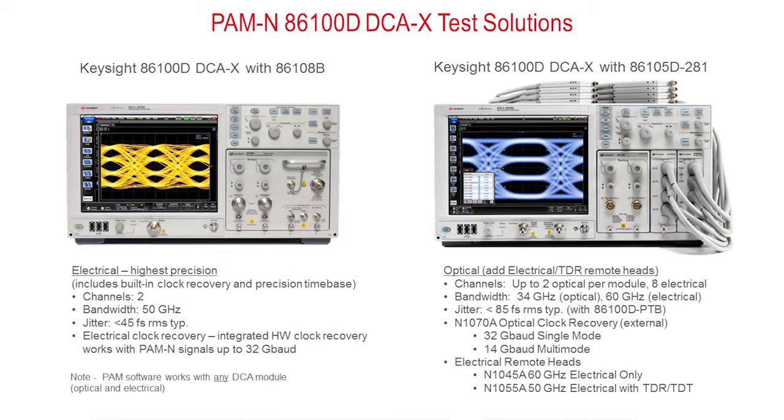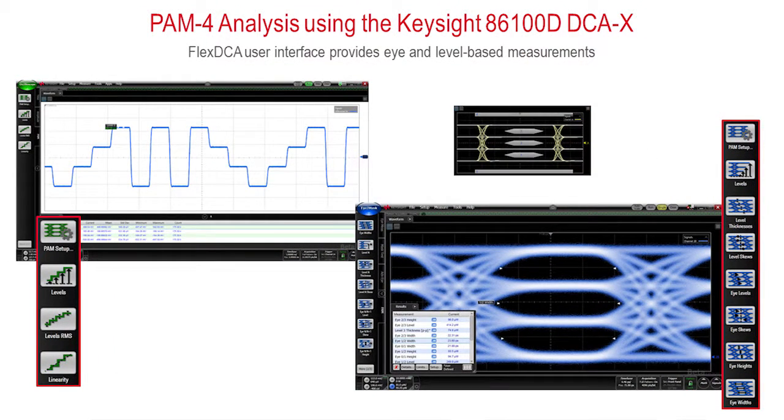Finally, in terms of making the analysis on the PAM-4 waveform, that's also quite simple. Essentially, what we have to do is give the DCA a sort of a slightly modified personality, a new measurement suite that is PAM-4 aware. And with PAM-4, there's essentially a license that we install, as well as a firmware upgrade, that gives it a new set of PAM-4 measurements.